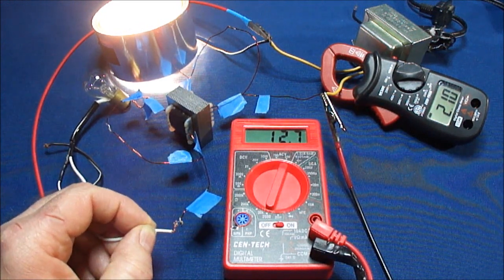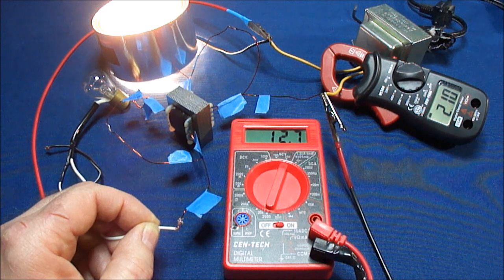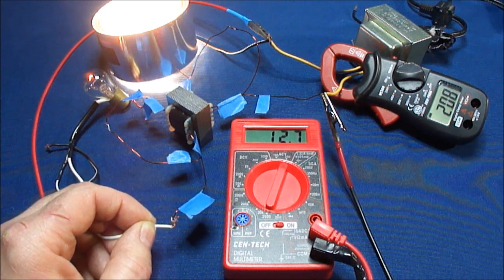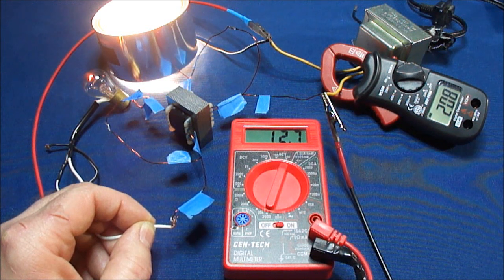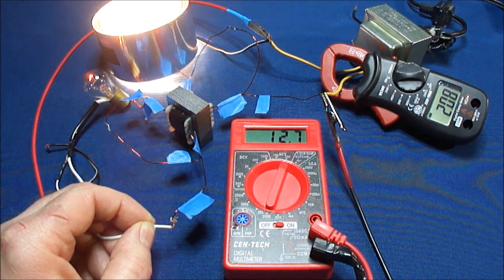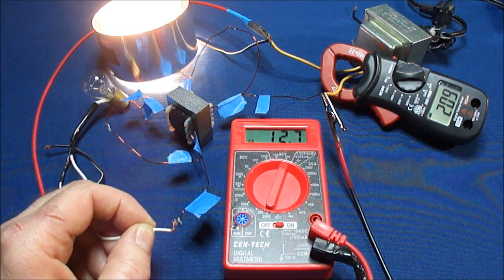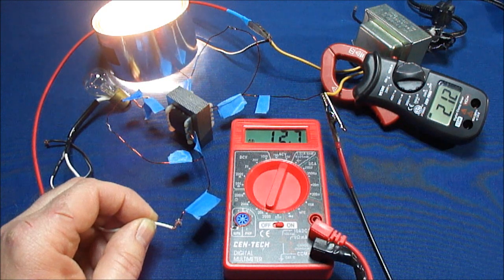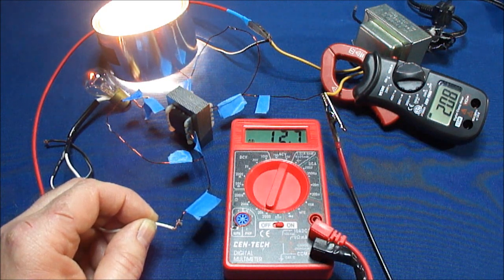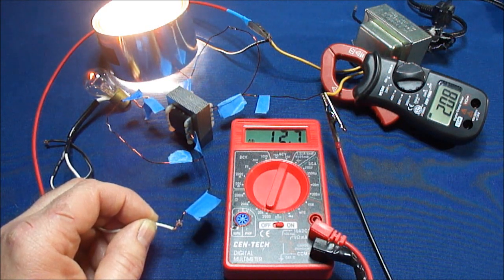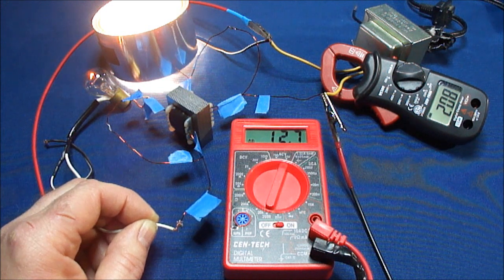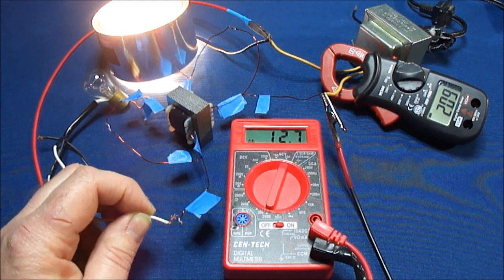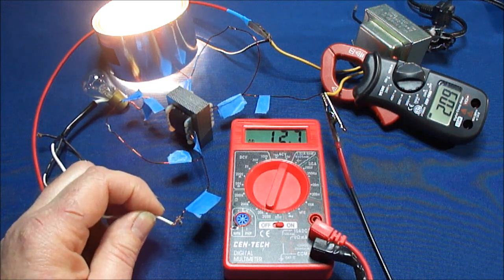Notice what happens when I connect the load on the secondary. The meter and the amps are both connected on the primary. Instead of the amps going up they are going down. All transformers I know when you connect the secondary the current is supposed to increase in the primary.